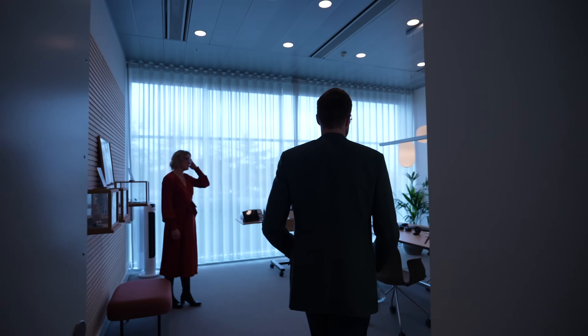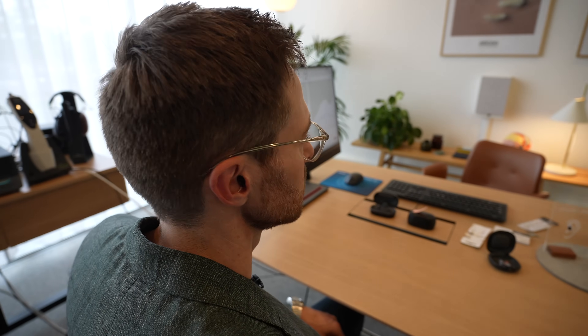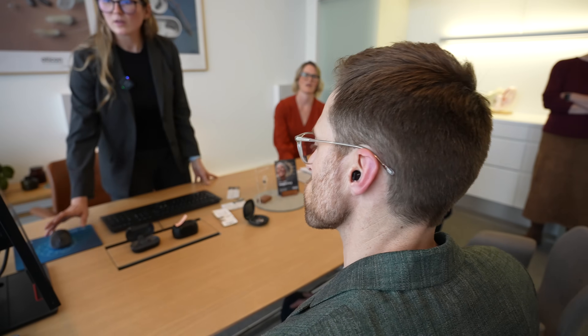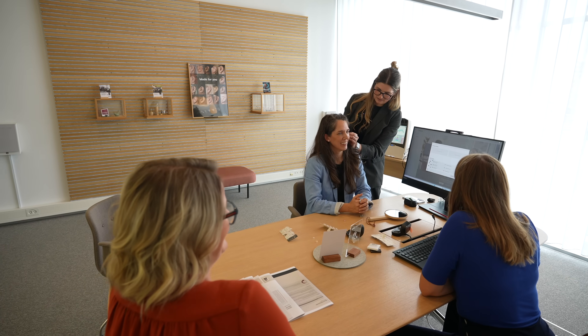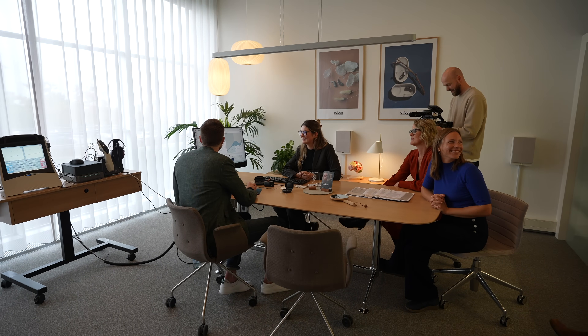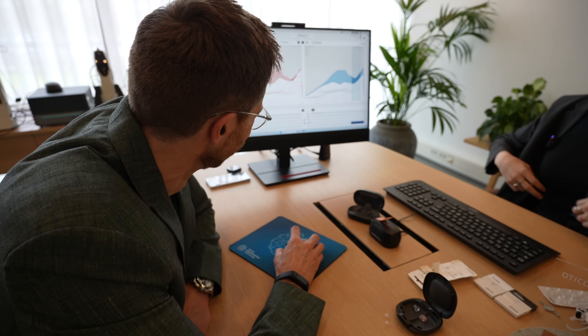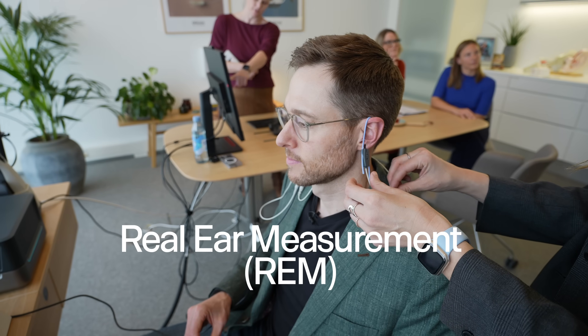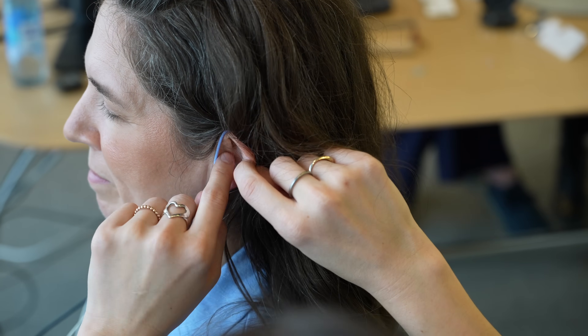During the fitting, I tested the Zeal with both a rubber dome fit and a custom earmold fit. For me, the custom earmold fit was better, surprisingly giving me plenty of amplification for this extremely small hearing aid. Ashley, on the other hand, was able to successfully use a rubber dome to get the amplification she needed. I also played around with the programming software, which I'm extremely familiar with from the Oticon Intent hearing aids, and performed real ear measurement to ensure I was hitting my hearing loss prescriptive targets — which I was pretty surprised we could achieve with a hearing aid this small.